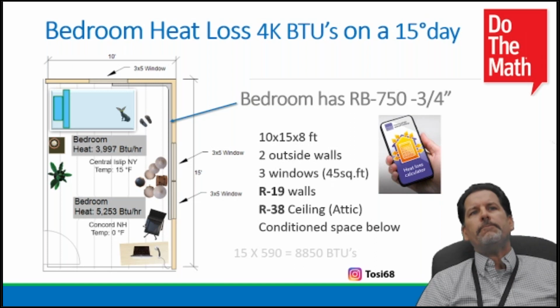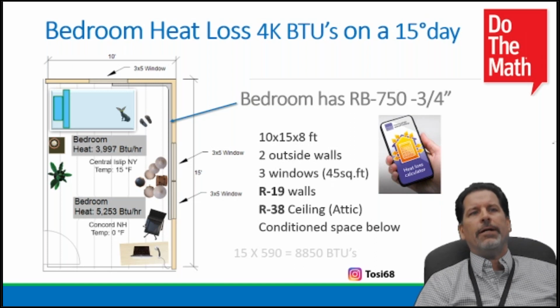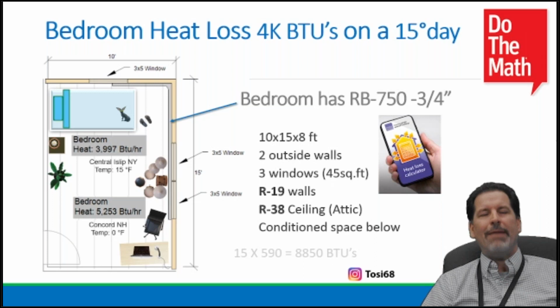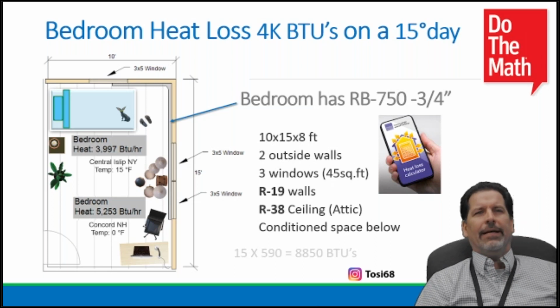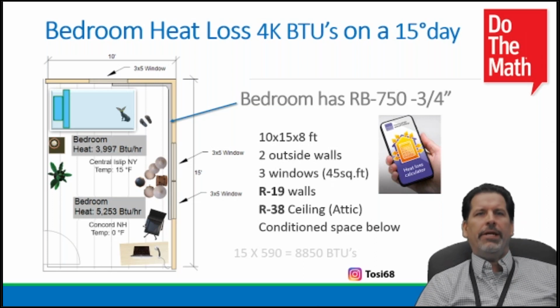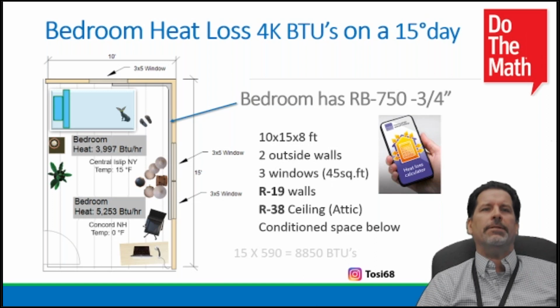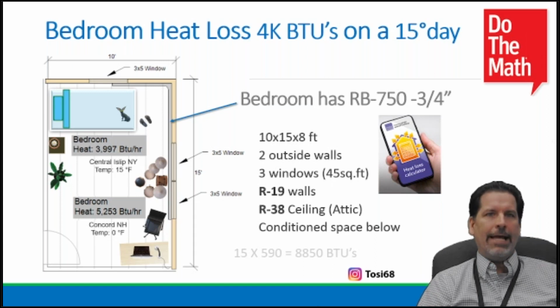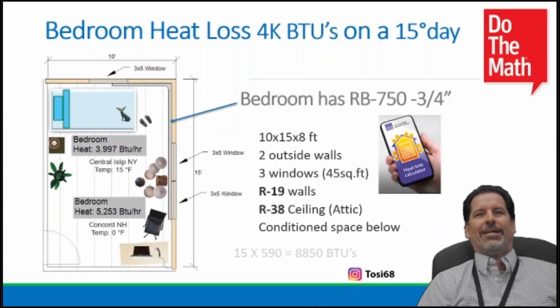Now, what I know to be true is that we're just maxing out at 180, and I looked at the charts, and you can see that what I need is 4,000, and I'm delivering close to 9,000 BTUs. Now, I don't know if that doesn't mean much to you, or what's the big deal anyway, but this is one room out of 10 rooms. So everything is grossly oversized. The boiler means it's probably grossly oversized.